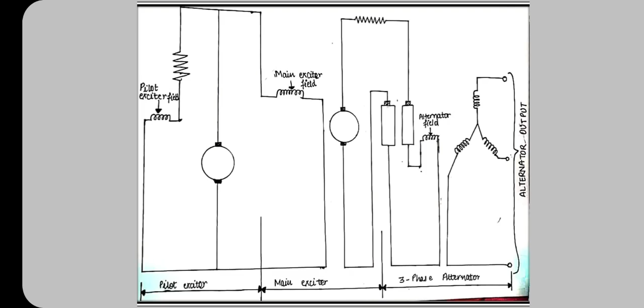The next method of excitation is the static excitation system for a synchronous generator. This figure shows the static excitation system. In a static excitation system, the power to the field winding of the alternator is taken from the output terminal of the alternator. For this purpose, the three-phase output from the alternator is fed to a three-phase step-down transformer called TR, and the step-down output from the TR is given to a thyristor bridge. The purpose of this thyristor bridge is to convert the three-phase alternating voltage into a controlled DC supply.